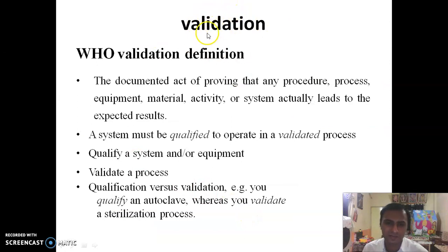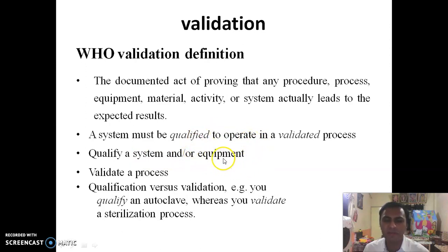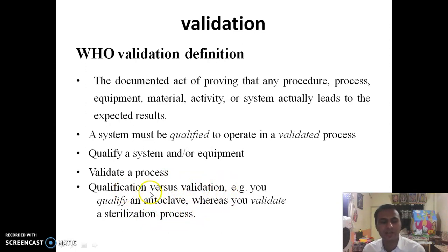Validation, as per WHO, is defined as the documented act of proving that any procedure, process, equipment, material, activity, or system actually leads to the expected results. A system must be qualified to operate in a validated process. For example, you qualify an autoclave, whereas you validate a sterilization process — that is the difference between qualification and validation.